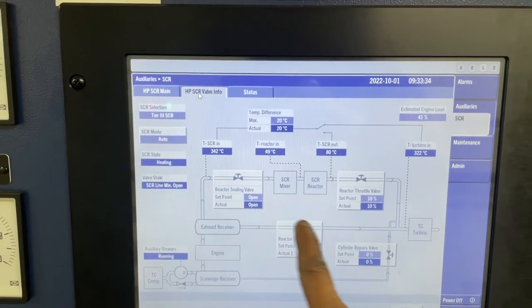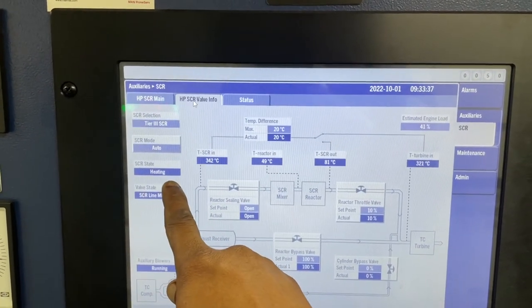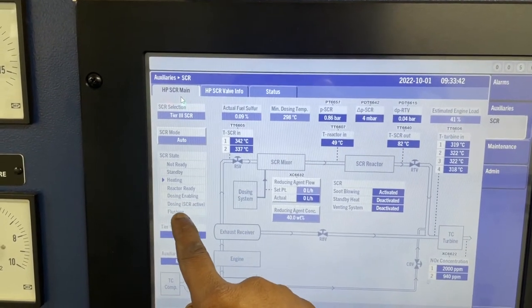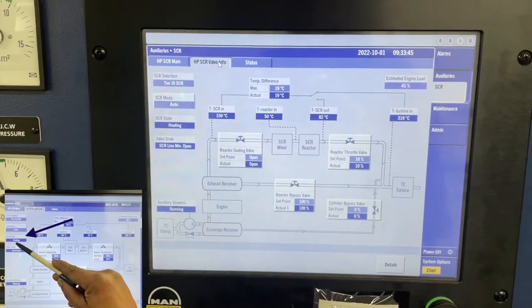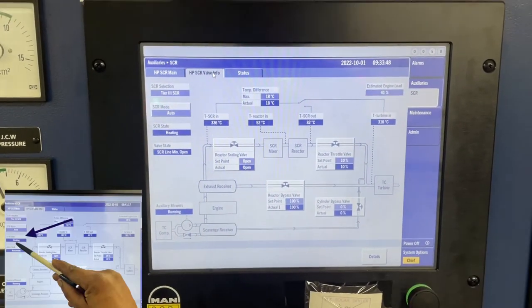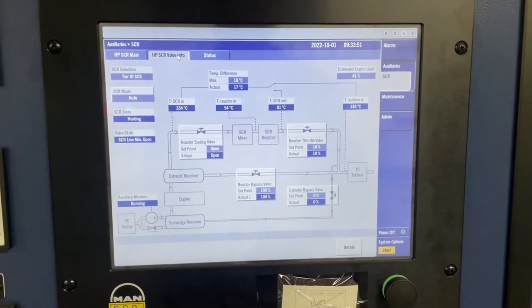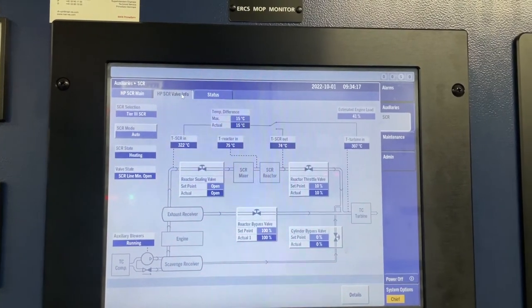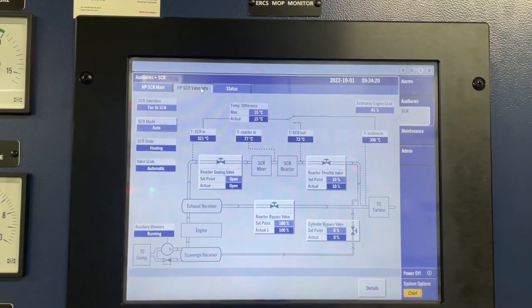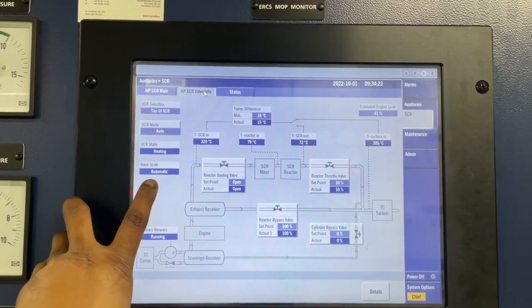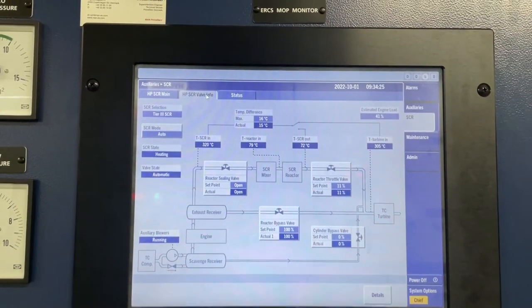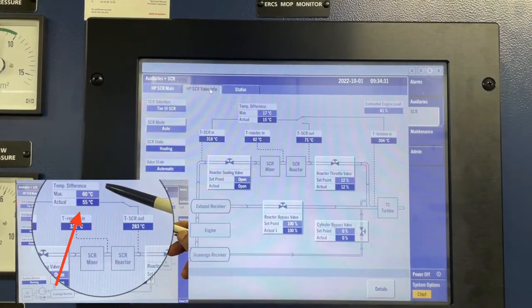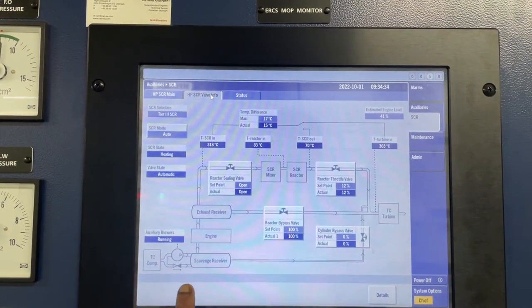As explained in my SCR valve function video, the SCR line minimum opening ensures that the turbocharger is getting enough energy. The SCR mode in heating continues until the SCR reactor reaches the ready-for-dosing temperature. In this period, the RTV will slowly regulate for opening, and at the same time this will ensure that the temperature difference between the reactor and turbine inlet stays within the predefined value.